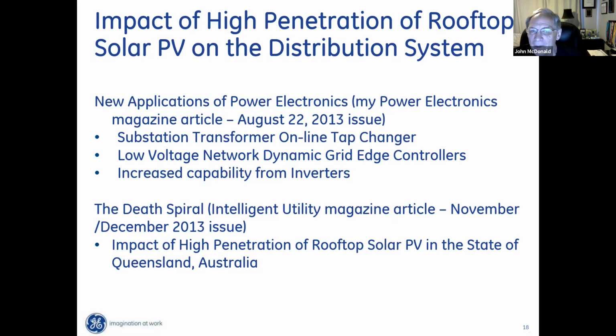As you know, there's a tap changer in the substation of a distribution feeder. The online tap changer is a mechanical controller, and its job is that as the primary voltage fluctuates, you want to keep the secondary voltage constant. You want the light bulbs in your house not to be real bright and real dim as the secondary voltage changes.